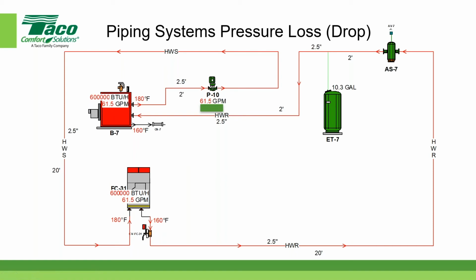So the very first thing we do, once we create this piping diagram, is this: I created this diagram using our HS2 software, but you could just sketch it out by longhand or whatever method you're using to represent the actual piping system. In this case, I know what the load is. It's 600,000 BTUs per hour, and I've calculated the flow in gallons per minute. I'm not going over those details in this presentation because this is all about pressure drop and not about capacity and load. So now I have an established flow of 61.5 gallons per minute, and I've decided to use 2.5-inch pipe, and I'll show you in a few minutes why I decided to use 2.5-inch.